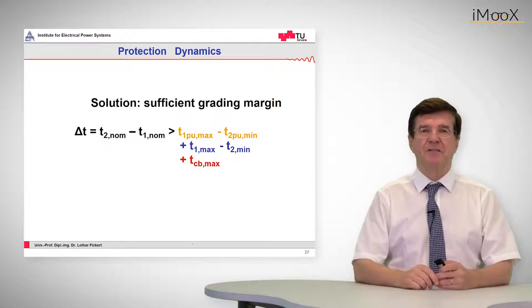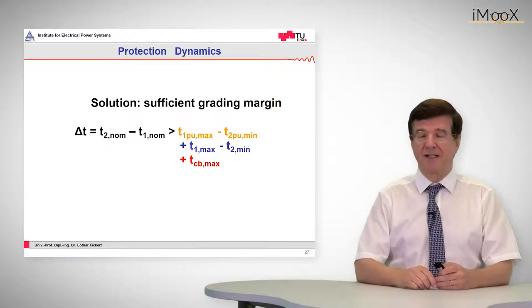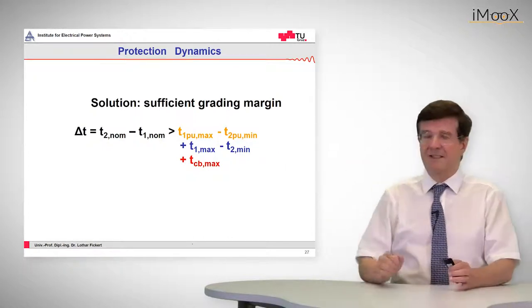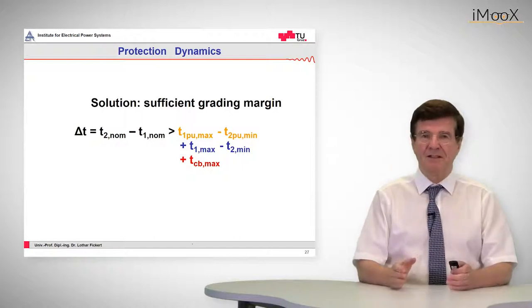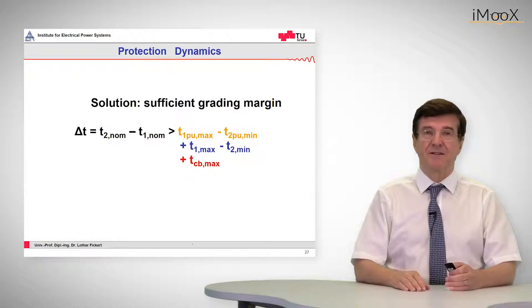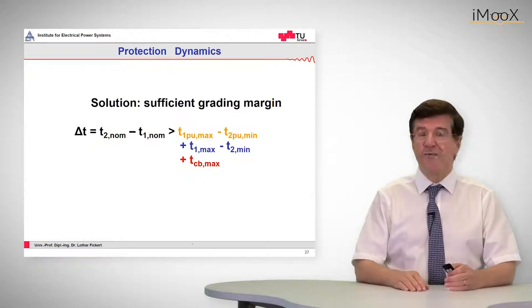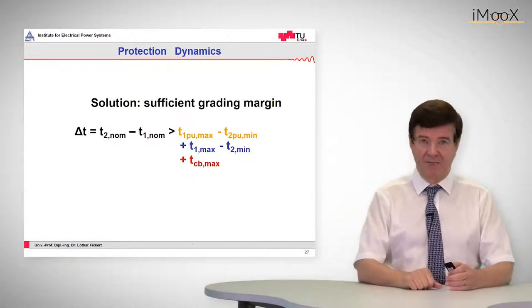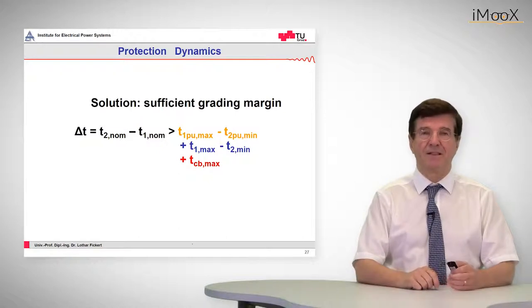Now there should be sufficient grading margin and the formula is written here. So it is the difference between the pickup times. It is additionally the difference between the delay times. And we must always take into account the circuit breaker, with its maximum arc clearing time.